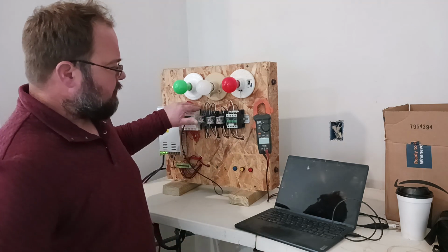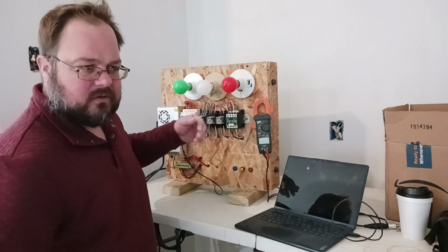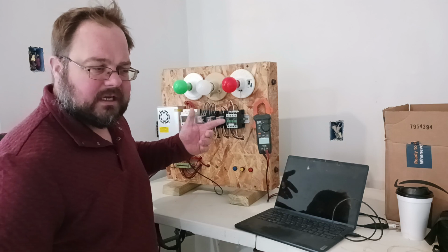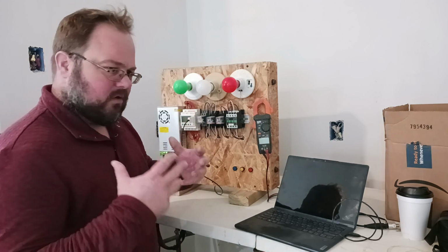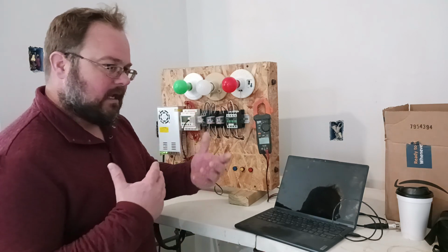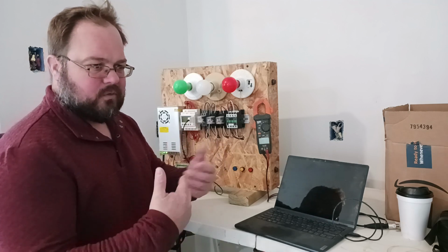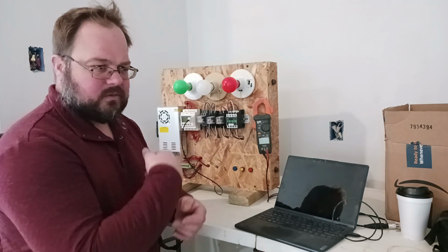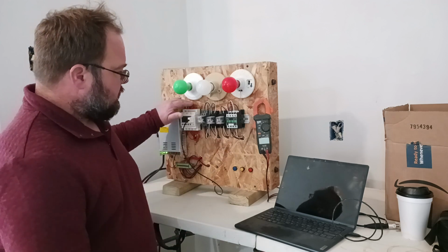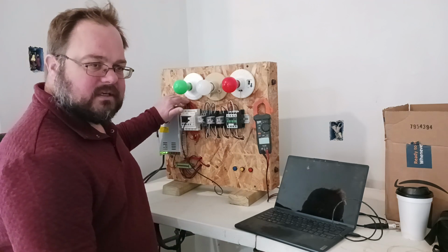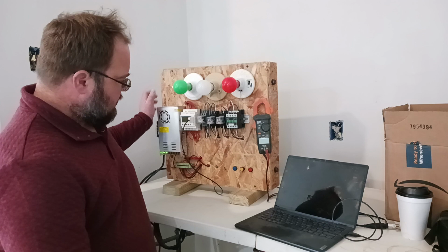If you have a lot of positive inputs, you want a PNP sensor, and if you have a lot of negative inputs, you want an NPN sensor. Of course, they do make universal sensors, but even those just have two wires, one negative and one positive for the signal, and you have to know which one to hook up. So just know that it does matter how you wire these inputs in, and this is on the positive side.